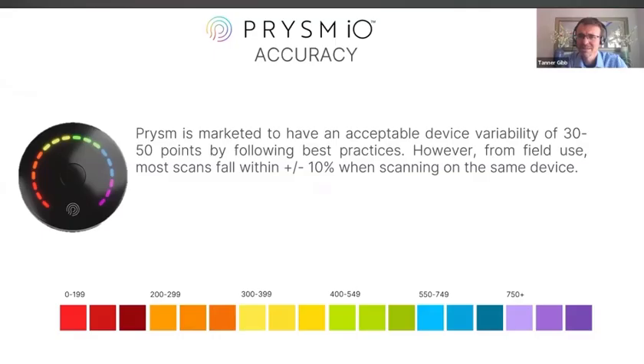Let's talk about PRYSM. It is marketed to have an acceptable device variability of 30 to 50 points by following best practices. That's based on the clinical study and the research that I just showed. So a very, very small difference in points you can expect to vary slightly from each scan. However, from field use, most scans fall within plus or minus 10% when scanning on the same device. So in controlled conditions, we see better precision compared to what we see in the field.